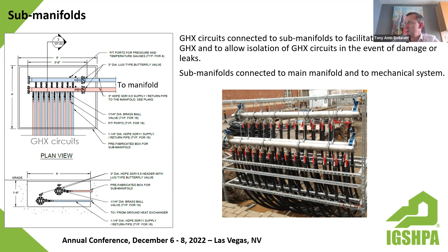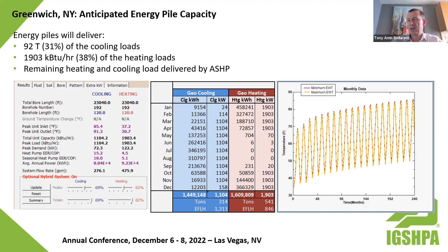On this 561 Greenwich project, the foundations themselves, we calculated that we could deliver 31% of the cooling and 38% of the heating load. There's a great solution with multi-stack where the heat pumps can operate in ground source mode or air source heat pump mode. But what they need to know is what is the most energy efficient way, so there's a control strategy that needs to be bolted onto this system that then enables the heat pumps on the roof of this building to operate in either ground source or air source heat pump mode.